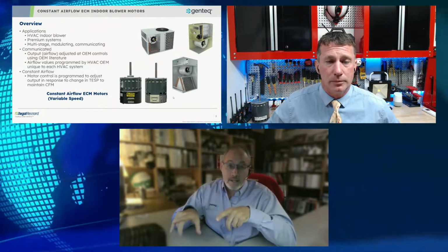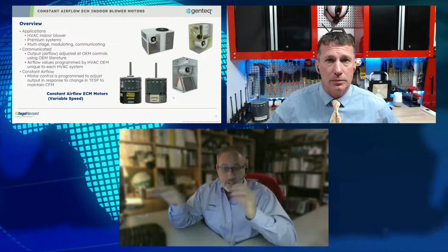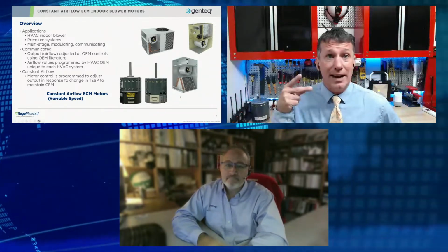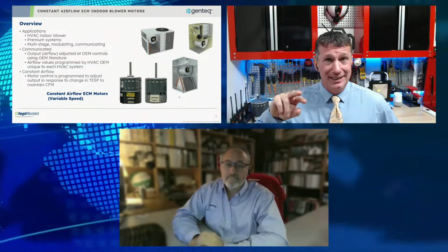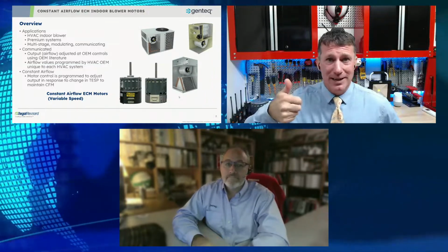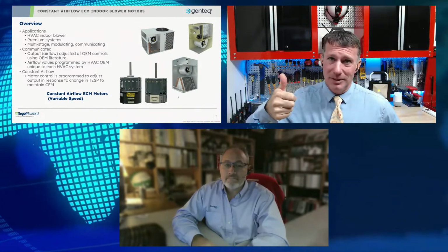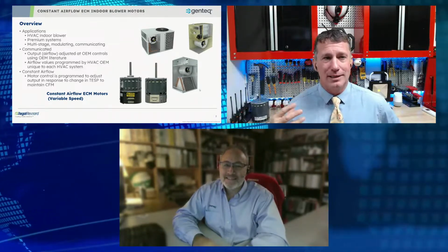Absolutely. So you need to understand that these motors are actually engineered not just by us, but also by the end user, which, my end user is the HVAC manufacturer, engineered by them to match the performance of each system that they go into. And some of those manufacturers have algorithms that work opposing from each other. So even if something happened to run, when you get a call for G, as the speed is demanded to increase, the algorithms could actually be calculating the opposite direction and slowing a motor down. But that's a whole other story.